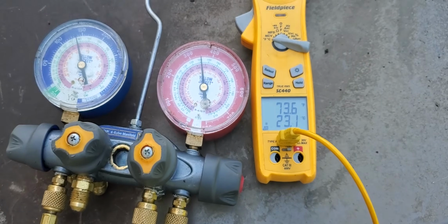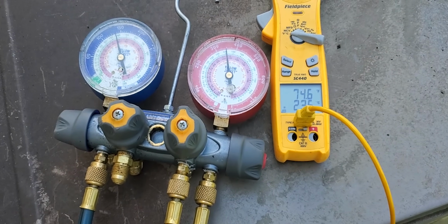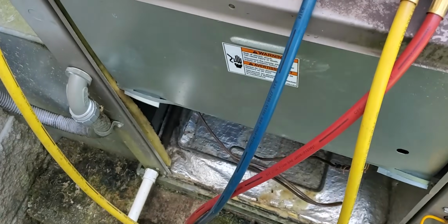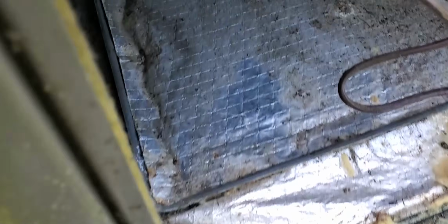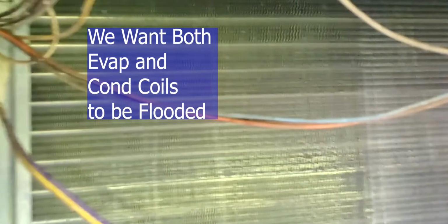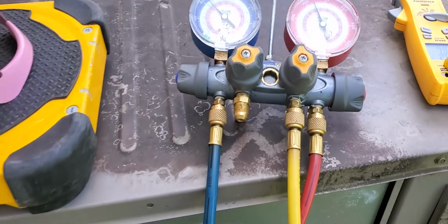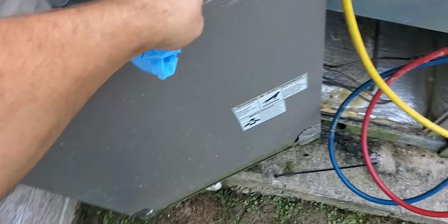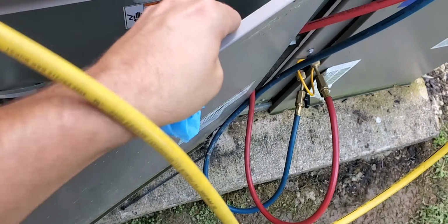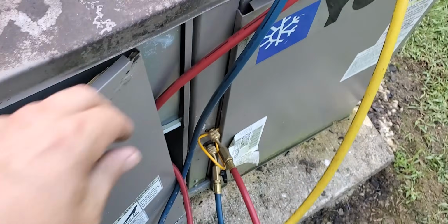As I'm making all these checks right here, you're going to be able to see these relative liquid temperatures and pressures. So by the end of this video, you ought to be able to go to another system and check refrigerant charge efficiently, knowing the values that you have to achieve for the system to have coils that have enough volume of refrigerant to operate efficiently.